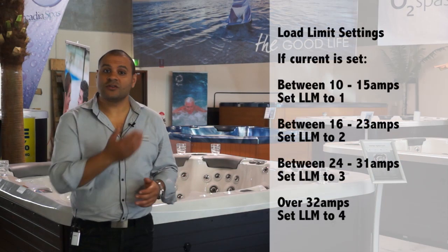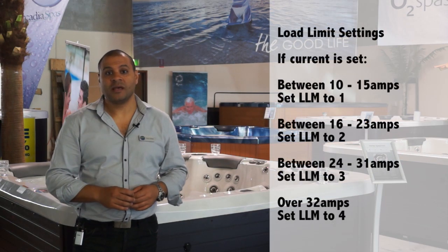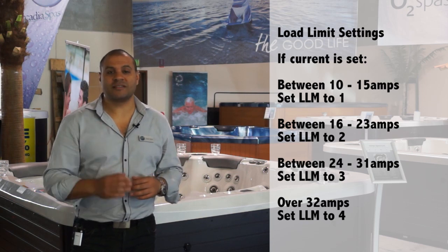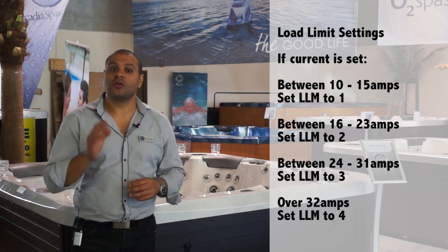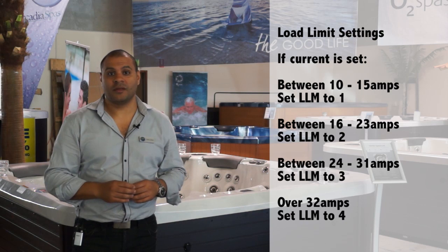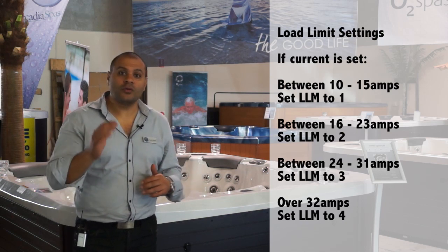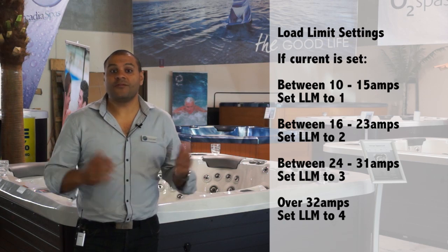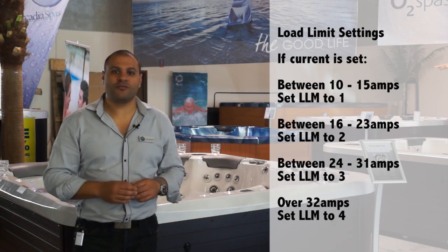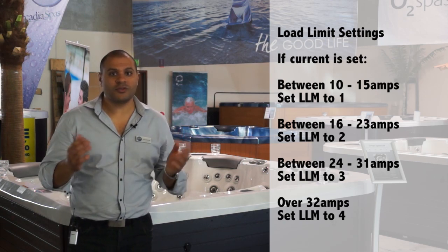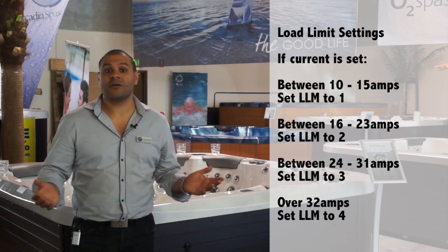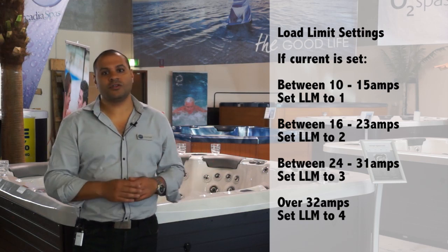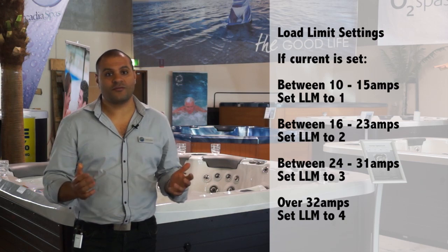Displayed here is a guide to your load limit setting. If your current is set between 10 and 15 amps, then the load limit should be set on 1. If your current is set between 16 and 23 amps, then the load limit should be set on 2. If your current is set between 24 and 31 amps, then the load limit should be set on 3. If your current is set over 32 amps, then the load limit should be set on 4.